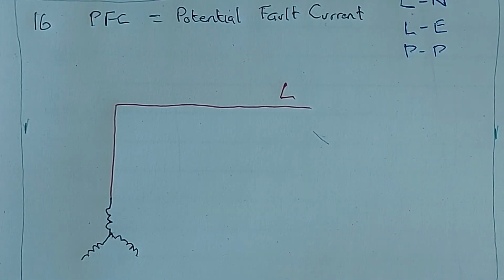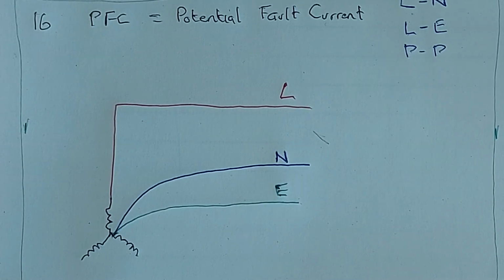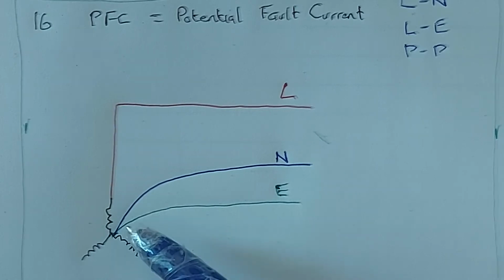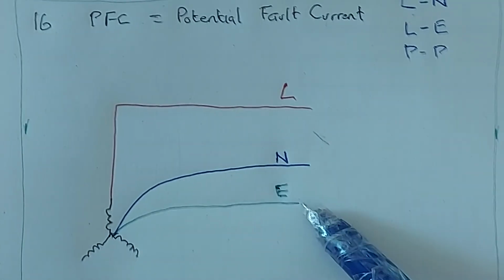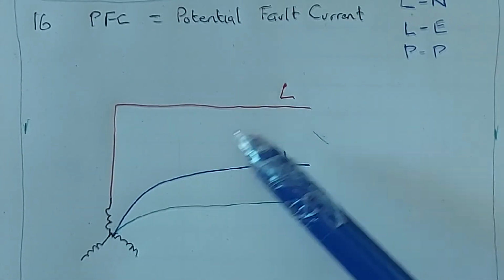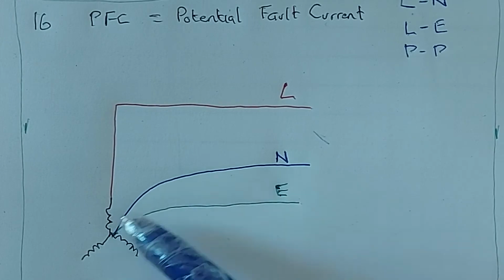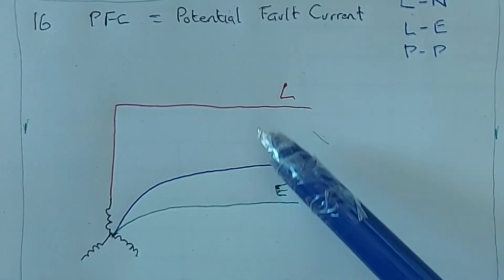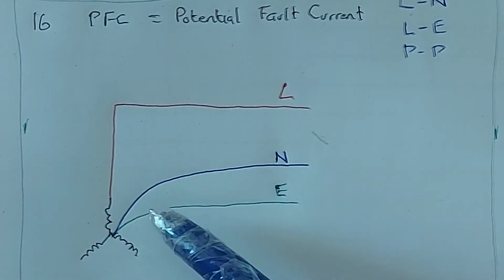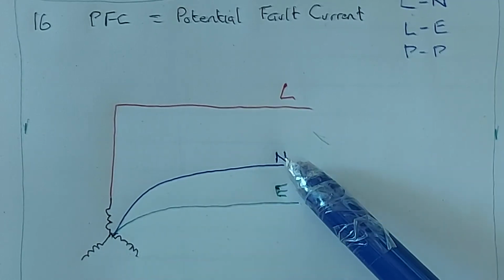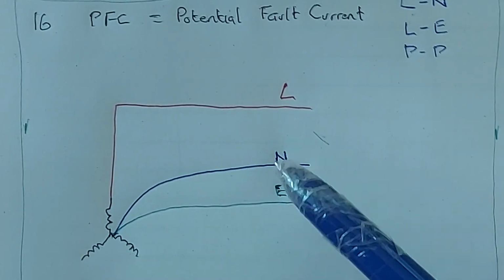So we've got our live, which is 230 volts, to neutral, or 230 volts to earth. And earth and neutral originate from the same point of the transformer. So between wherever our voltages are, there could be multiple fuses through different distribution boards to get to this point. The earth and the neutral will always be continuous though. The neutral could be switched, providing it's switched at the same time as the live. Earth is never switched. The neutral can go through what we call neutral bars or neutral links, but it should always be connected unless there's some sort of testing going on.